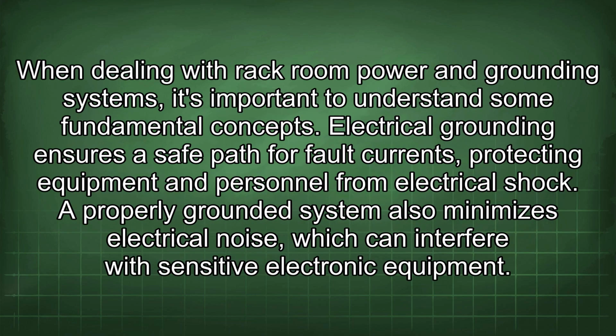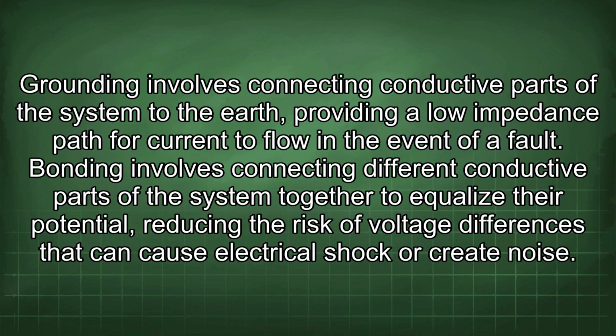When dealing with rack room power and grounding systems, it's important to understand some fundamental concepts. Electrical grounding ensures a safe path for fault currents, protecting equipment and personnel from electrical shock. A properly grounded system also minimizes electrical noise, which can interfere with sensitive electronic equipment. Grounding involves connecting conductive parts of the system to the earth, providing a low impedance path for current to flow in the event of a fault.